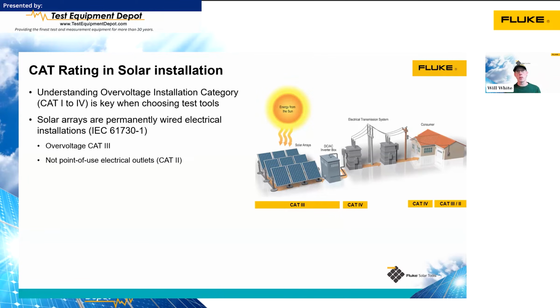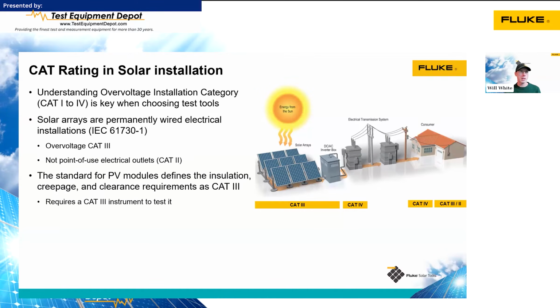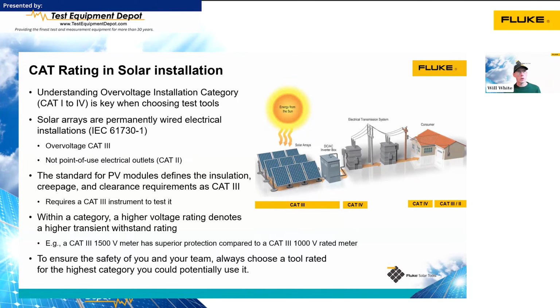Then category 2 is our branch circuit wiring. That's things like our outlet circuits, lighting circuits, things like that. There is actually a category 1, that's things that are not connected to an electrical system. So a solar street light would be an example of that. So we know that a solar array is a category 3 environment. We need to have tools that are rated for that category rating.